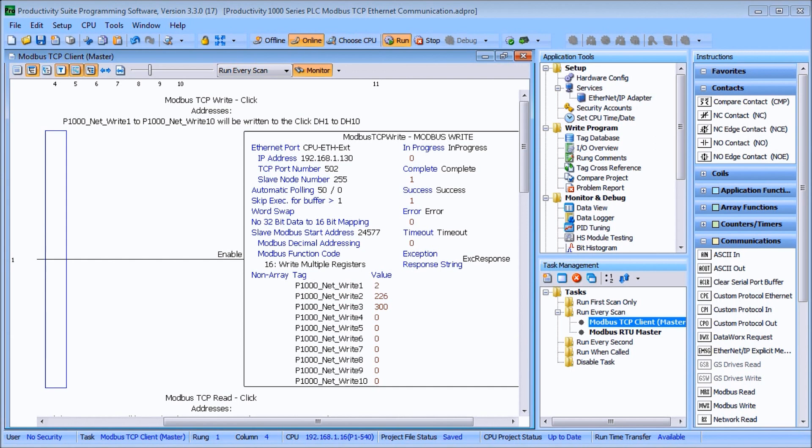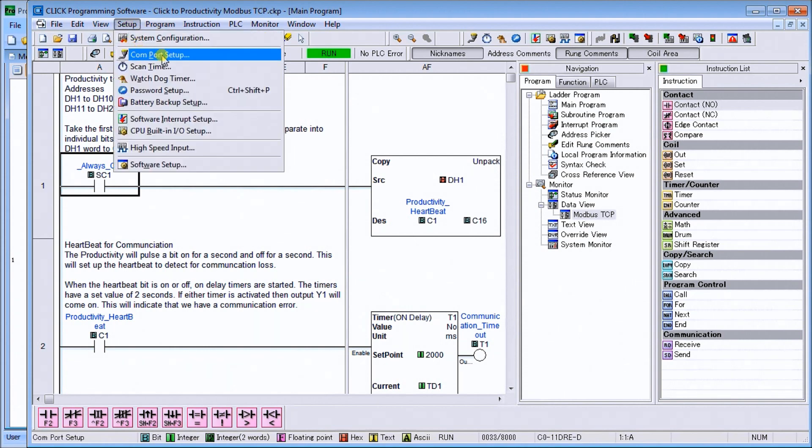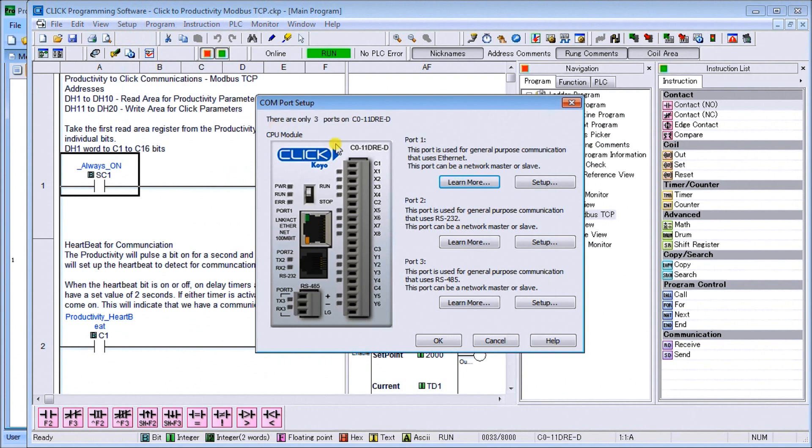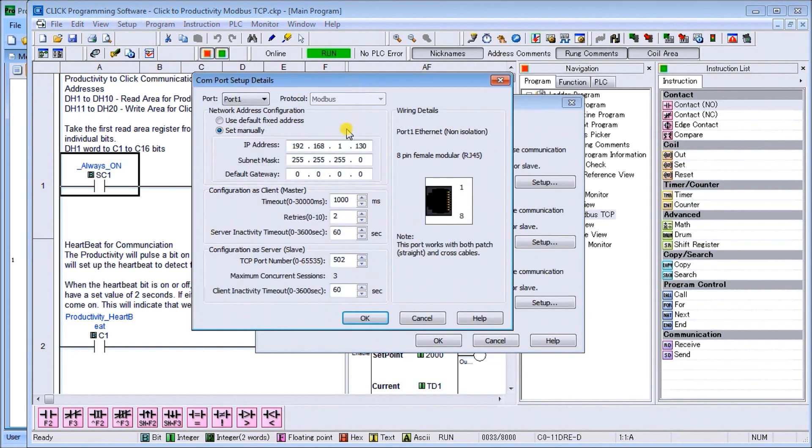Let's get started. On my screen you'll see my Productivity series PLC software running, and we'll call up our Click PLC. The first thing we need to do is actually set up the communication port. Let's look at the setup and we'll go to Com Port Setup. This will be on port number one, which is our Ethernet port. You can see here that in port number one, here's our IP address which is 192.168.1.130 with subnet mask of 255.255.255.0.